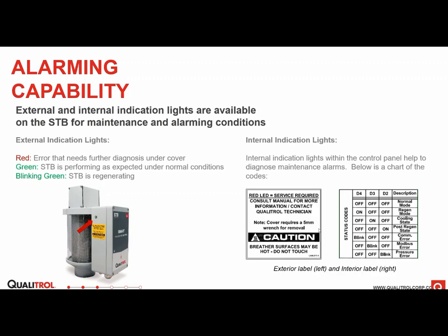So we still have 3 LEDs that will tell you the current status of the breather. Inside the enclosure, right on the PCB, we have 3 board-mounted LEDs. So if you see a red LED on the outside, you can open the enclosure and do further field diagnostics from the 3 board-mounted LEDs. They'll tell you all of the same error states that we had on the previous generation with the front-facing 3 LEDs, but now they're on the board. And you can see here, they'll tell you normal mode, regeneration, cooling, post-regen, communication error, Modbus error, pressure error.